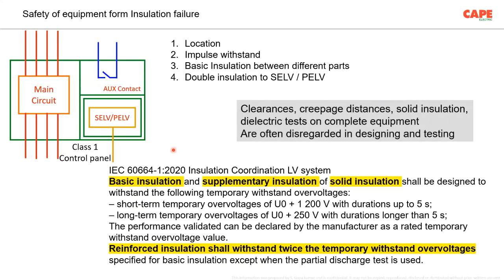So the applicable technical points you should take care of in this case are clearance, creepage distance, solid insulation and dielectric test, which are often disregarded in designing and testing in our electrical installation. If these points are taken care of very well, your equipment is able to withstand the stress voltage. There are 2 points. One, the stress applied to your equipment must be limited to a certain level. Two, your equipment must be able to withstand a certain level. This level is U0 plus 1200 volt between line and neutral up to 5 seconds, as in the previous slide which I have shown you.